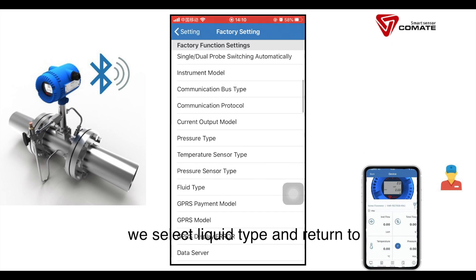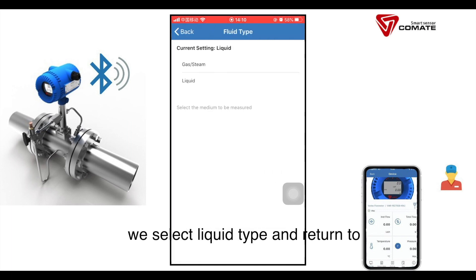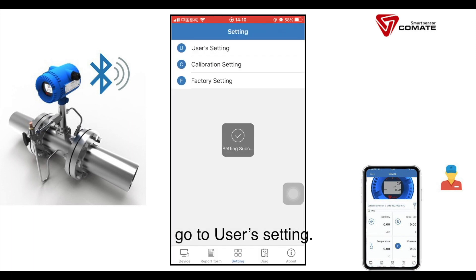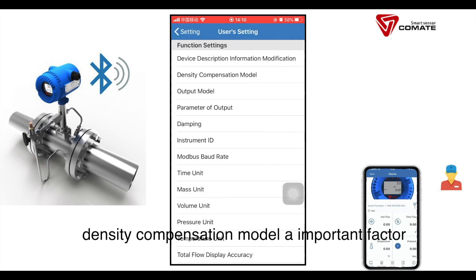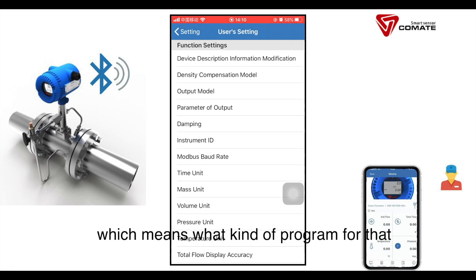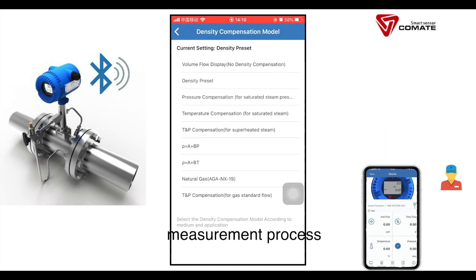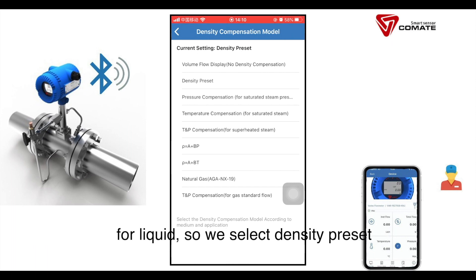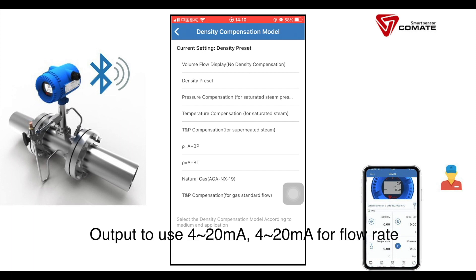We select liquid type and return to go to the user setting. Density compensation mode is an important factor, which determines what kind of program is used for the measurement process. Because this application requires mass flow output for liquid, we select density preset.